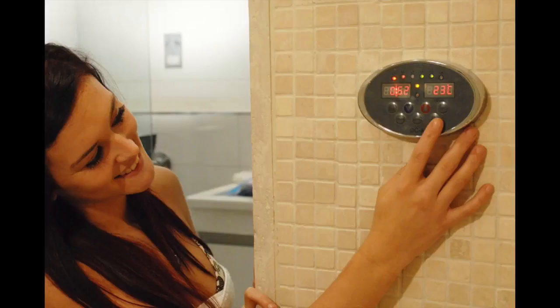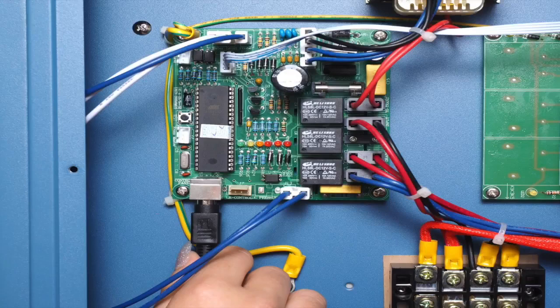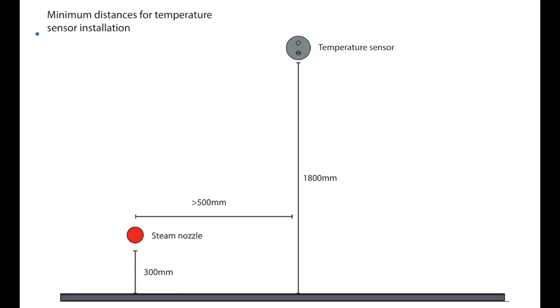The keypad can be installed inside or outside of the room. The connection lead is 5 meters long and plugs into the circuit board as shown in the image. The temperature sensor plugs into the keypad and has a 4 meter lead. This should be positioned at 1800 millimeters from the floor and as far from the steam nozzle as possible.